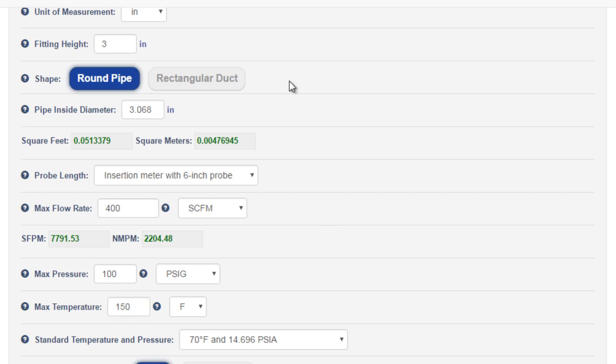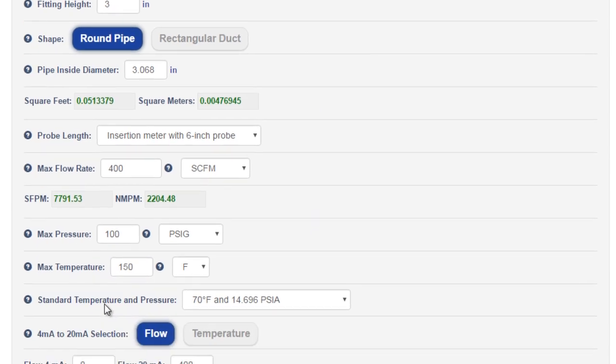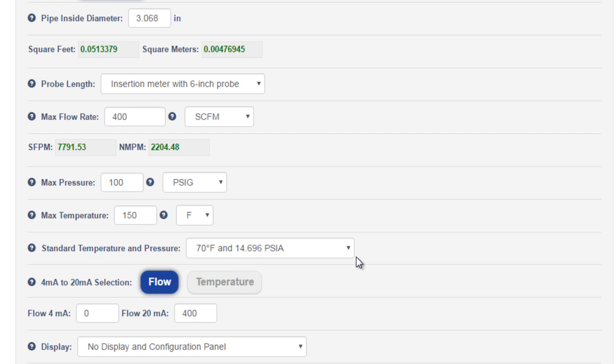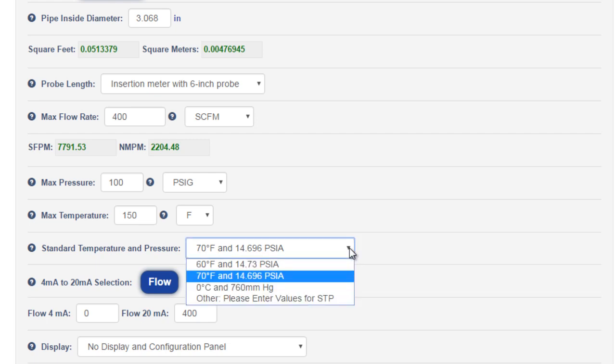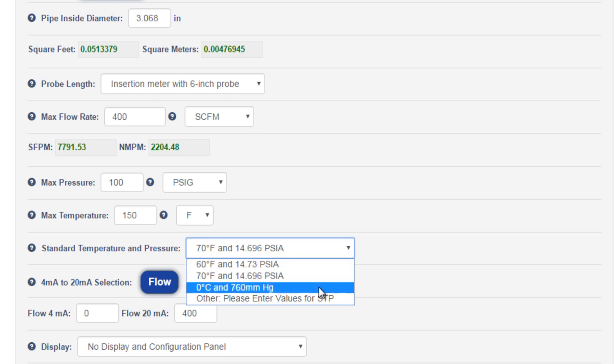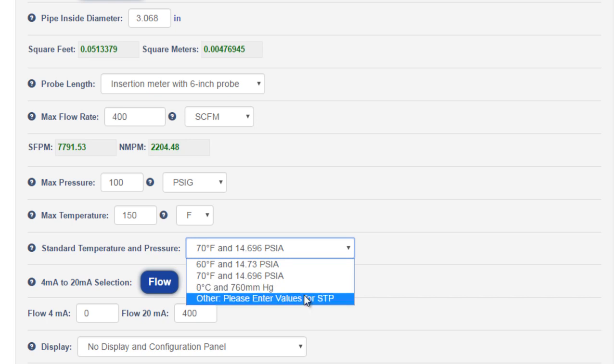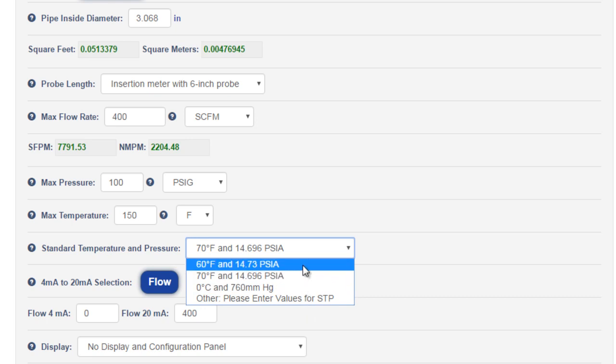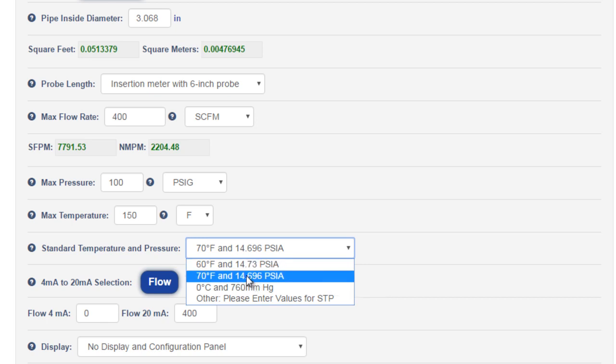Based on the gas we chose earlier, a standard temperature and pressure will be recommended. For air, that STP is 70 degrees Fahrenheit and 14.696 psi. The other standard options available are 60 degrees Fahrenheit and 14.73 psi for natural gas applications and 0 degrees Celsius with 760 millimeters mercury. You can also enter in custom STP values. Keep in mind that these are only reference temperatures and pressures. They do not directly correlate to any of the process conditions in your application. We'll leave this at 70F.